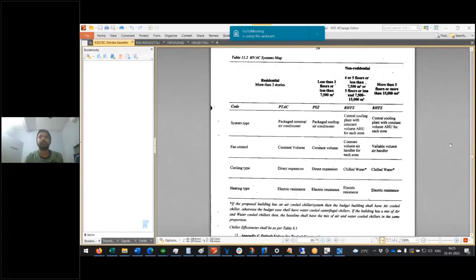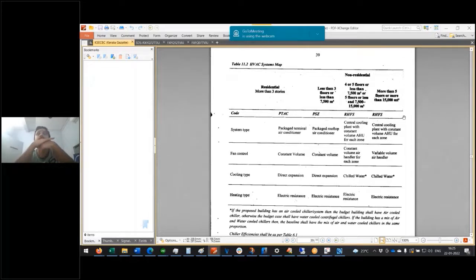Okay, so we have a 7-floor building, built up area 3000 square meter. Can we use VRF for the base case model? No, we cannot. That's the clear cut answer, because this falls under this category. 7 floors. Clearly, you have to go for a central plant in the base case, which is a chilled water plant. So you cannot model VRF.